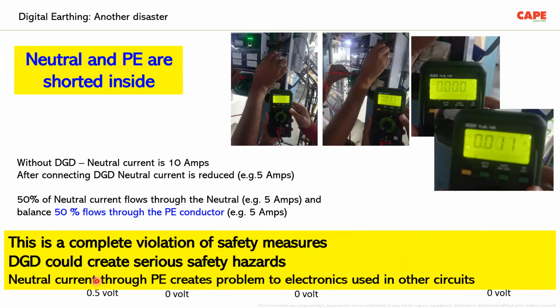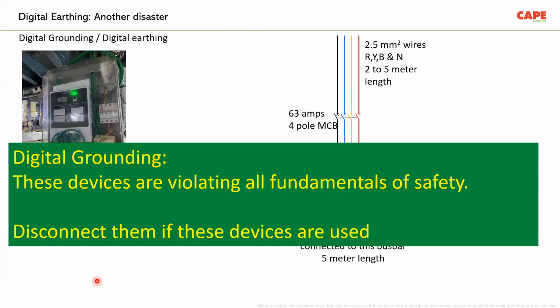Actually, this is a complete violation of safety measure. Digital grounding device could create serious safety hazards. Neutral current to PE creates problems to electronics used in these circuits. So what I recommend is, if you have purchased this device by mistake and if you have already installed it, my humble request is, please disconnect these devices if you are using them. Please, please disconnect it, because these devices will create more trouble for you.